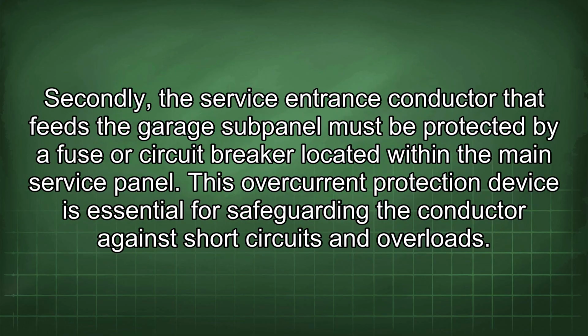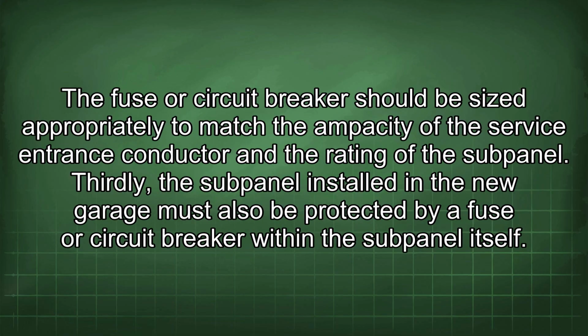Secondly, the service entrance conductor that feeds the garage subpanel must be protected by a fuse or circuit breaker located within the main service panel. This overcurrent protection device is essential for safeguarding the conductor against short circuits and overloads. The fuse or circuit breaker should be sized appropriately to match the ampacity of the service entrance conductor and the rating of the subpanel.